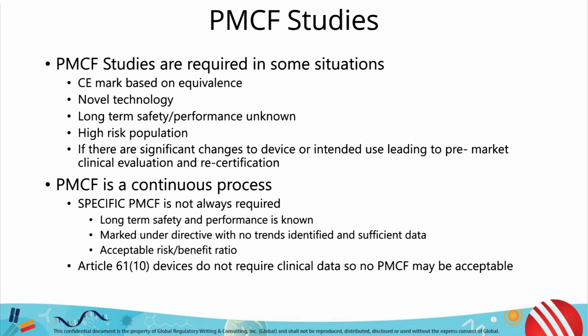However, in many situations, specific PMCF is not required. If the device's long-term safety and performance is known, if the device was marked under MDD and there are no concerning trends identified, and if the risk-benefit ratio is acceptable and based on sufficient clinical data.